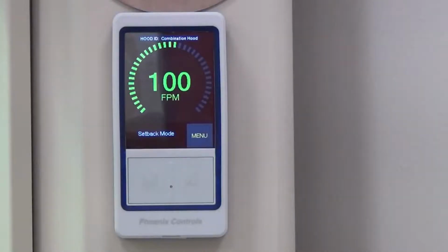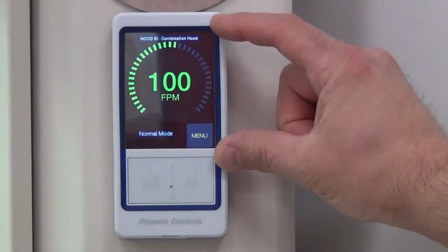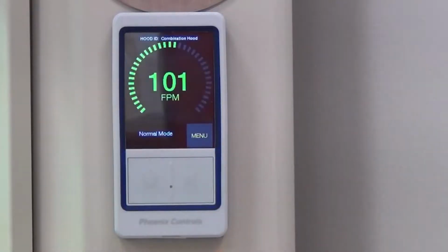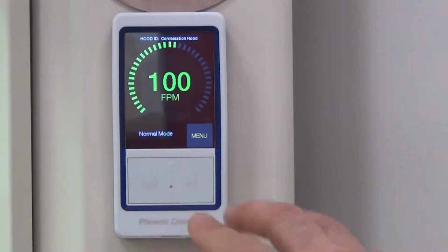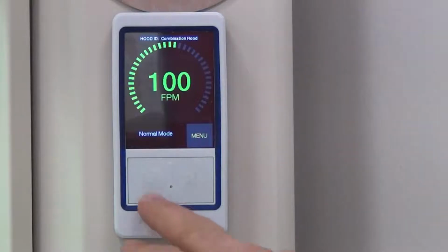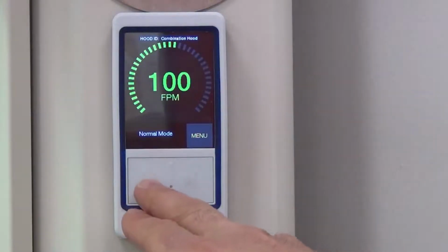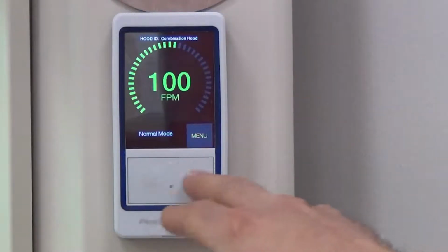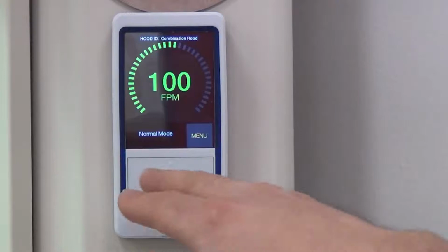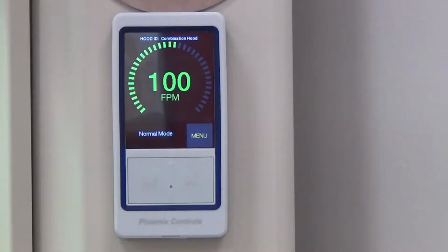So this Sentry fume hood display was kind of based on the size and functionality similar to a smartphone. So in the top portion of the screen up here, we actually have a touch screen built into it. So all of the functionality, the menu and things like that are all based on a touch screen. Down here in the bottom, again, safety being paramount for our products, we realize that when you're using fume hood displays or you're using fume hoods, you're probably going to have a glove on, and not all touchscreens react when you're wearing a glove. So we made the safety features, the fume hood exhaust, which is the emergency exhaust if you had a spill, and the mute function to be tactile buttons. So in the case that I had a spill and I needed to emergency exhaust my fume hood, I don't have to take my glove off to push the button.